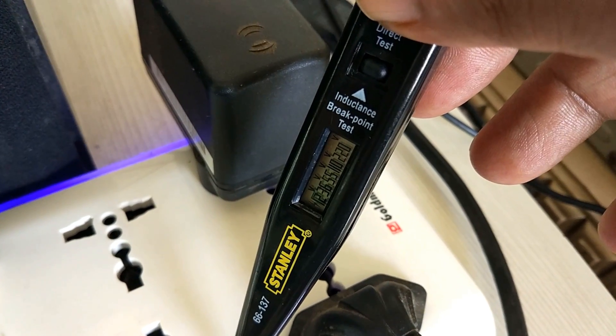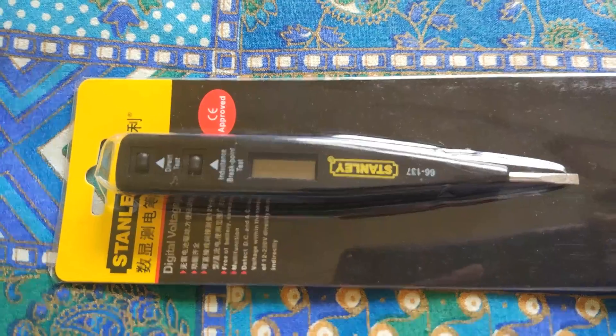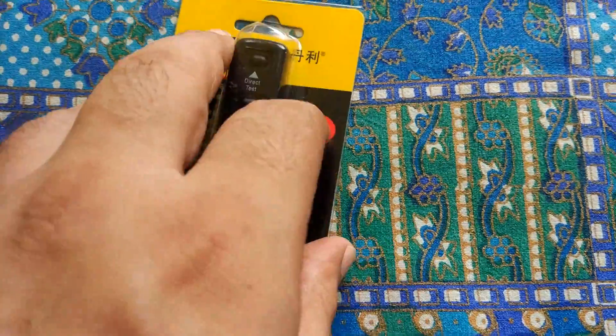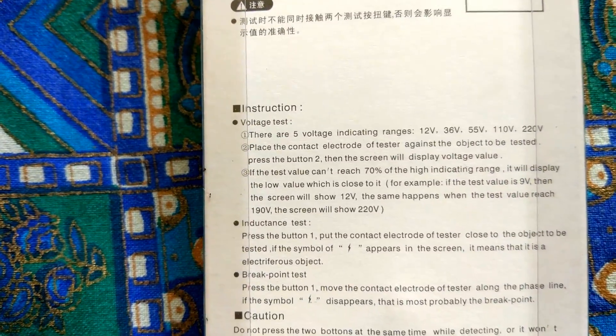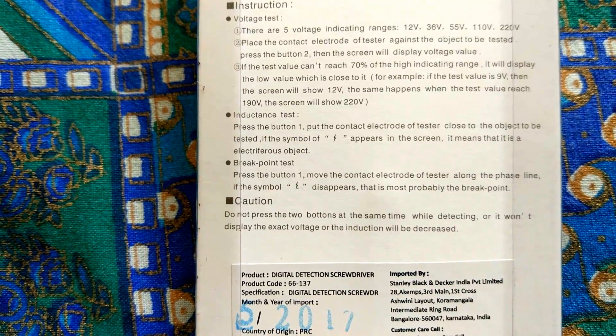Touch button number one or button number two — button two for a direct test and button one for an indirect test. When you bring the electrode close to the object, a power symbol appears on the screen, which means the object is an electriferous object — basically, current is flowing through it. For the breakpoint test, press button number one and move the contact electrode along the phase line.